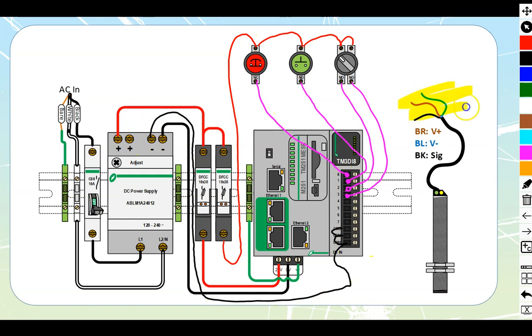Our last component that we have over here on this side is going to be a sensor. We've got the European standard wiring for this one. North American standard is red and black for positive, negative. In Europe, they do use the brown for positive, the blue for negative, and then the black is going to be the signal. We want to connect this thing onto ours. So what we will do is we will run out from our power supply over here another negative. We'll just take that one all the way across the top over here. And this thing needs to go to my negative line. Lots of mistakes get made in North America where people try to use the black as the negative.